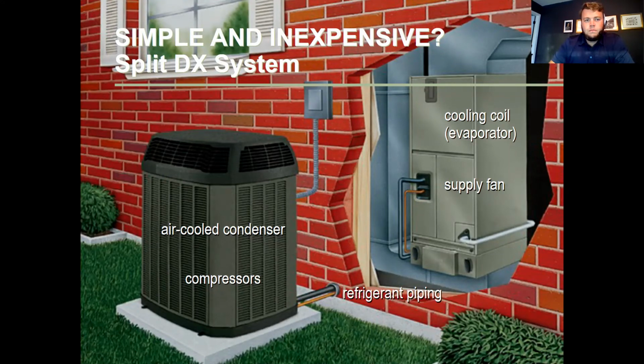Okay, so this is what I think we're all pretty much familiar with, the way split systems look. We probably have one in our homes that looks a lot like this, where there's a condensing unit sitting outside that has a compressor and a condenser in it. Inside, we've got an air handling unit that's got an evaporator coil, and there's tubing that connects the 2 pieces together. Most of these systems use a simple wall thermostat to control the compressor. It just cycles the compressor off and on to maintain the space temperature. And that's usually adequate for a house.